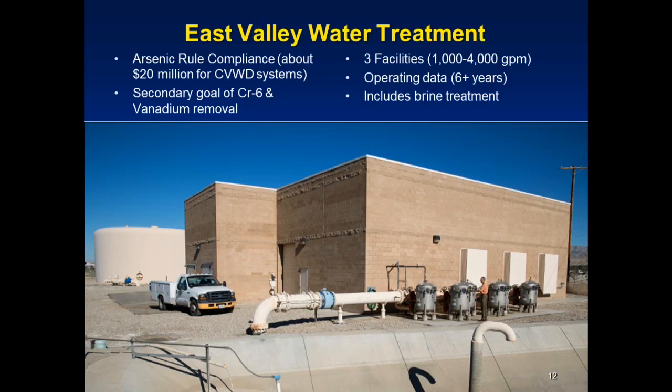It's an ion exchange process, kind of similar to a water softener. Instead of removing calcium, which makes the water hard, it's removing sulfate and a little bit of chromium and arsenic. Little tiny beads are in there with lots of surface area. And that's where the chromium and the sulfate and the arsenic attach to the bead. And they trade those. Chloride is let go and it accepts sulfate. So it's an exchange process. So that's why they call that an exchange.